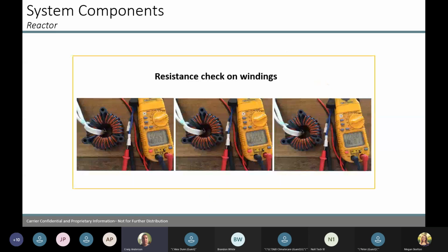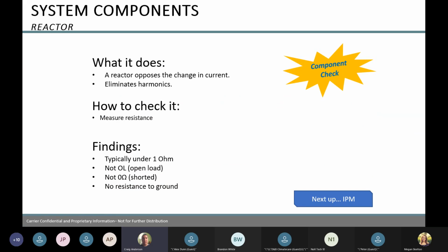To check the reactor, anything we deal with DC voltage, we're usually checking resistance on the windings, whether it's a compressor or a motor, similar to our reactor here. We're checking the resistance between the windings. So on this one here, a reactor, what does it do? It's cleaning our power going to the next step. How do we check it? We're going to check it for resistance.